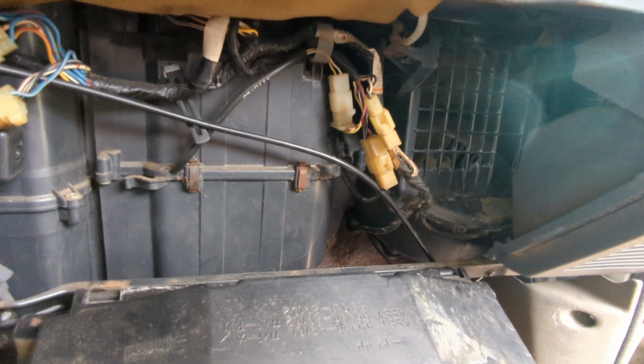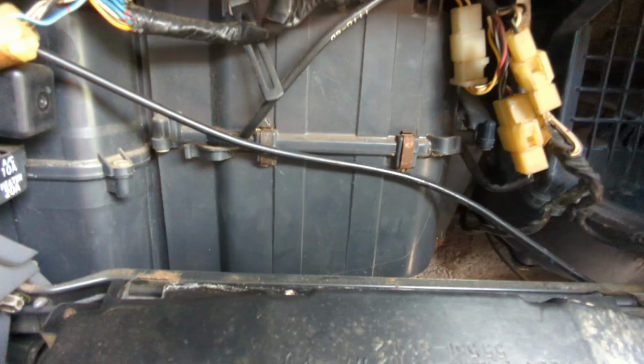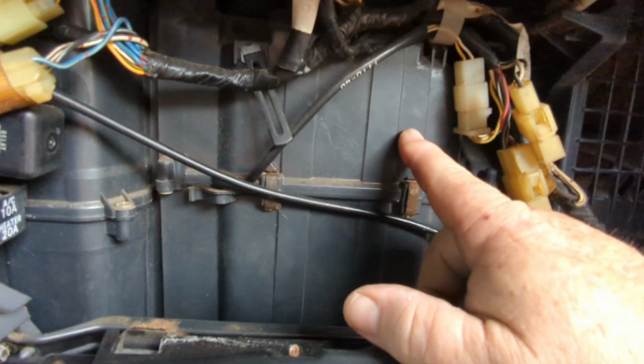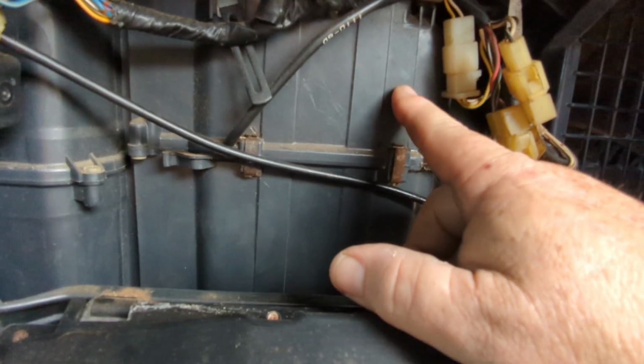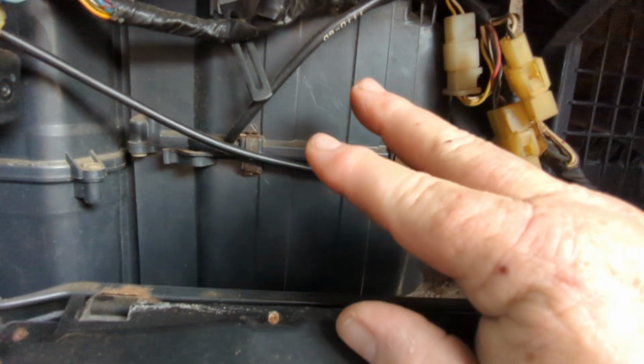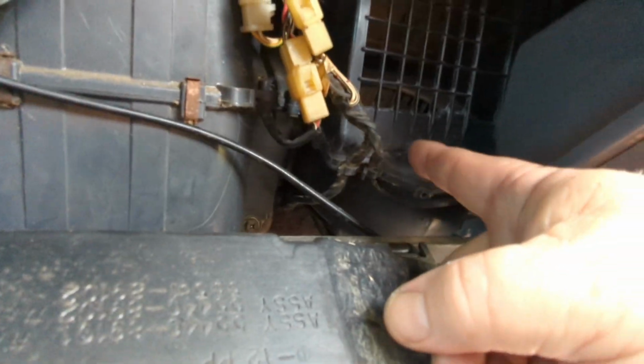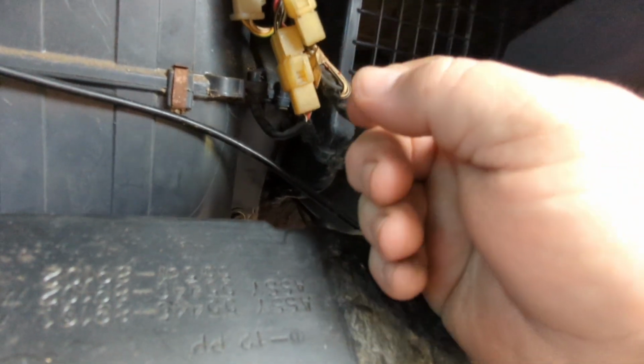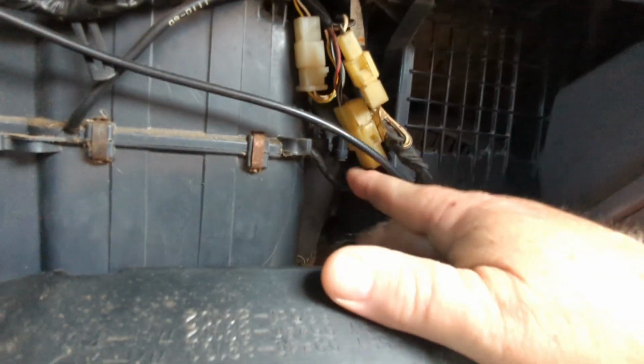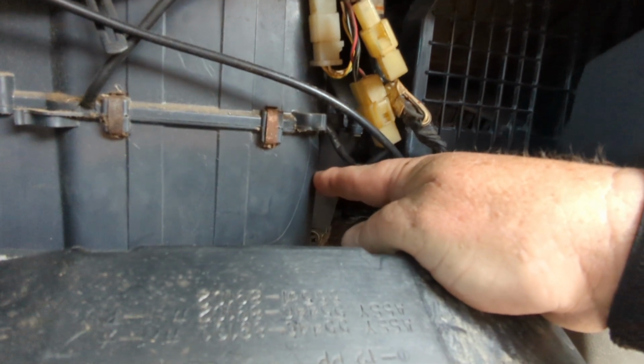So I'm going to take a peek at that evaporator and see what it looks like. This is the box that contains the evaporator. You can clean these in place, and there's two ways to do that. One, pop out the blower motor and peep up in there with a phone, or one of those borescope, endoscope things.